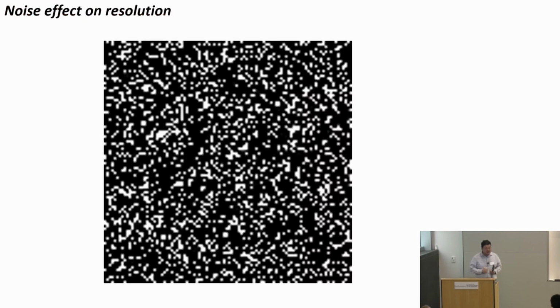However, there's one additional factor that has not been incorporated, that is noise. This is because when Abbe developed the diffraction limit, most microscopy was transmission microscopy. If you lack photons, you shoot more photons in there. But nowadays, with modern microscopy, most of us are dealing with fluorescence, and each single molecule gives you about 500 to 1,000 photons. Then they disappear. So we are always photon starved.